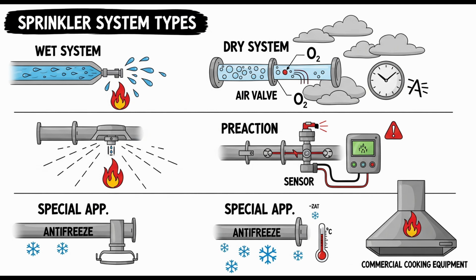Finally, for refrigerated spaces, the requirements for fire detection used for pre-action system release get very detailed. This seems like a critical area. Absolutely. For pre-action systems installed in freezers, which are common precisely because they keep water out until detection confirms a fire, the detection system that trips the main pre-action valve must normally be designed to operate prior to any of the automatic sprinkler heads activating from heat. Detection first, just like standard pre-action. How is that achieved in a freezer?